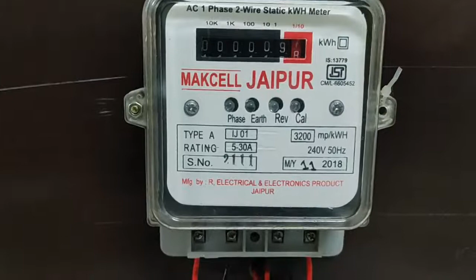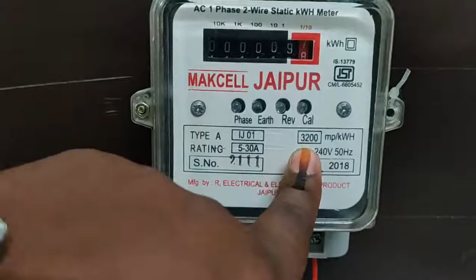Students, we are going to measure the meter constant error here to calibrate the energy meter. What is a meter constant? It is the number of revolutions per kilowatt hour. Here you can see the mentioned revolutions to get 1 unit of power, that is 3200 revolutions. That is, to get 1 unit of energy, the meter has to rotate 3200 revolutions.